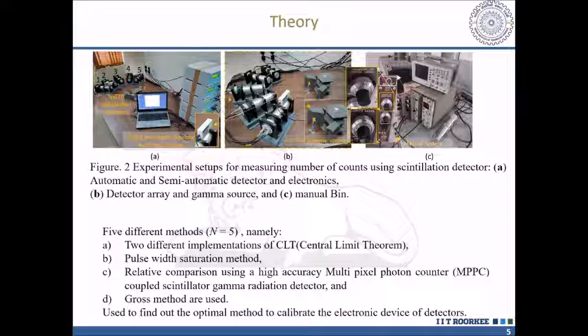The fourth one is based on the comparison of counts measured using the sodium iodide thallium scintillator detector with a high accuracy multi-pixel photon counter coupled scintillator gamma detector. And the fifth one is the gross method. According to this method, the optimal parameter value has the highest ratio of the square of the gross sample count rate to the background count rate. Using these methods, we have calculated 5 optimal settings, one from each method. Now, the next step is to figure out which setting is best among those calculated from the 5 different methods.